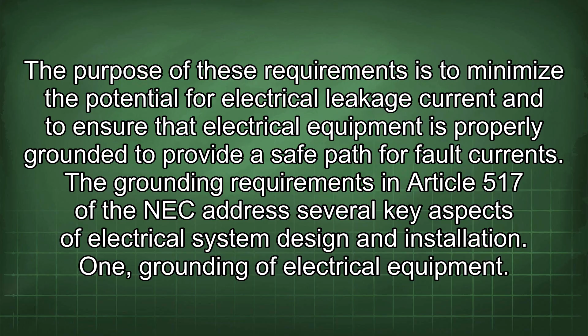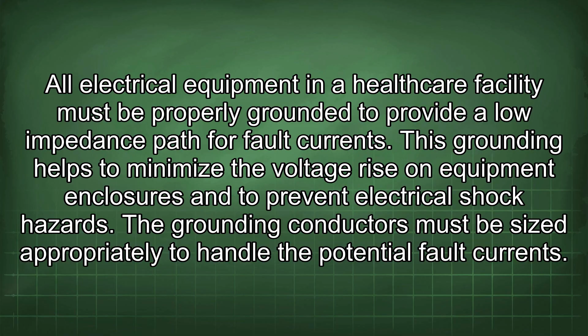The grounding requirements in Article 517 of the NEC address several key aspects of electrical system design and installation. First, grounding of electrical equipment: all electrical equipment in a healthcare facility must be properly grounded to provide a low impedance path for fault currents. This grounding helps to minimize the voltage rise on equipment enclosures and to prevent electrical shock hazards. The grounding conductors must be sized appropriately to handle the potential fault currents.